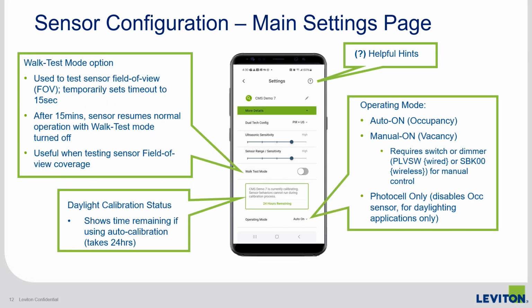Below the range slider, you have the option to put the sensors in walk test mode. This is useful when testing the field of view to confirm proper coverage and whether the sensitivity needs to be increased or decreased. The timeout is shortened to 15 seconds in this mode. When finished, you can toggle the walk test to off, or after 15 minutes, it will automatically shut off and resume normal operations.